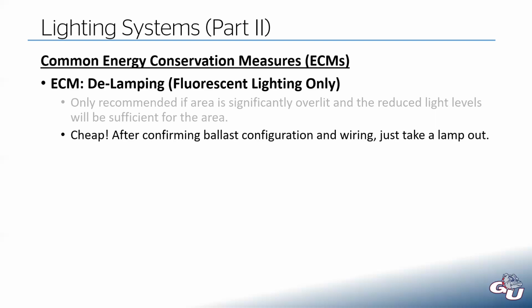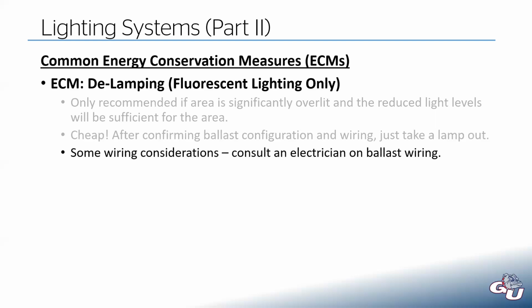You do have to look at your ballast wiring. The short version is you have to make sure the ballast is wired to your lamps in parallel. If they're in series and you take a lamp out, you've just broken the circuit. But if they're wired in parallel, you can take a lamp out and still have the remaining lamps powered through the ballast. So there are some wiring considerations there—consult an electrician, don't do it yourself.